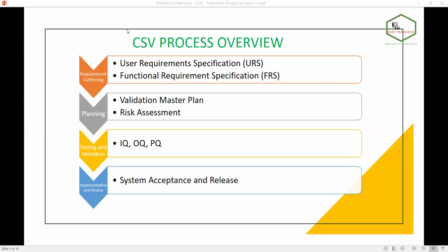After performing performance qualification, you need to ensure system acceptance, whether your requirements meet your criteria. You prepare a quality summary report so that you know whether your software, instrument or application meets your criteria as well as regulatory compliance. After that the software can go into release mode. We need to prepare a traceability matrix and validation summary report, then the software is moved into the production environment, meaning day-to-day use. The complete validation process is completed this way, and we call it the software development life cycle. In your training, you will get a very detailed explanation of each deliverable.